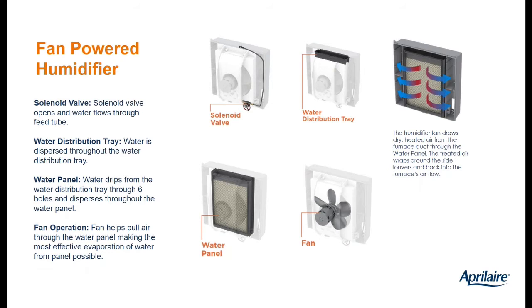The humidistat calls for humidity, the water valve opens, and the fan turns on inside the Model 700. Water runs down the water panel. Air moves through the water panel, evaporating some of the water. That water hits the back of the 700 and then has nowhere to go but to circulate back into the HVAC duct through those 4 side openings that you see there indicated by the arrows. That humidified air then gets mixed with all the air being moved by the HVAC system and dispersed throughout the ductwork.